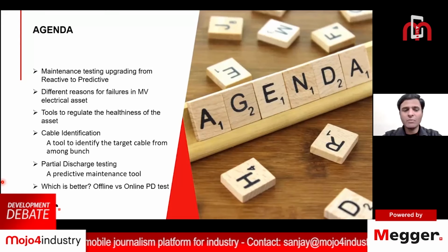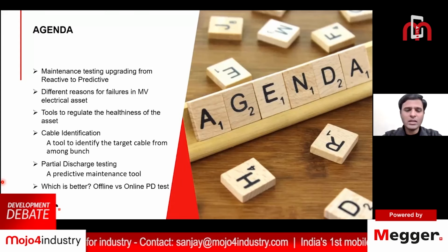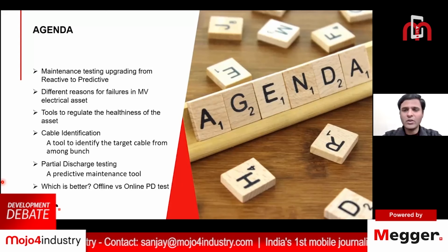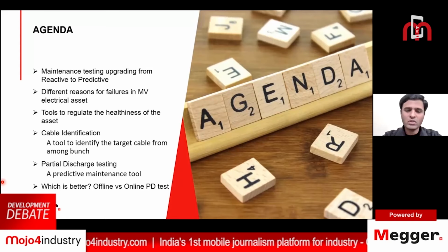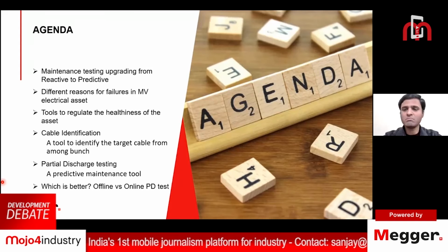And we will be studying partial discharge testing, a technology which is very much accepted by the market and the industry, and there are a lot of advancements which have come up in partial discharge testing. And finally, we will be putting up a question like whether an offline test maintenance work is preferred or an online maintenance test is preferred.